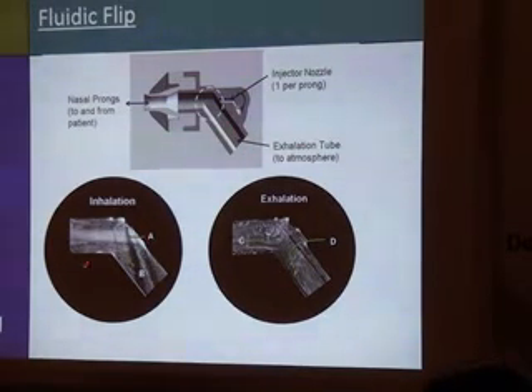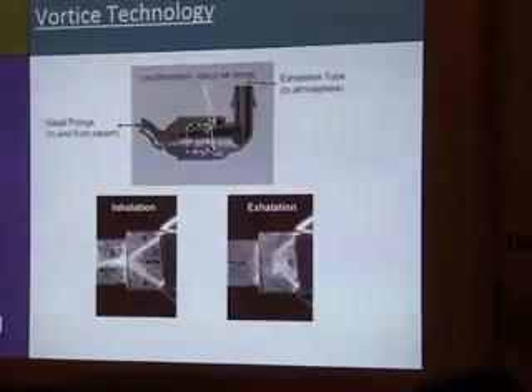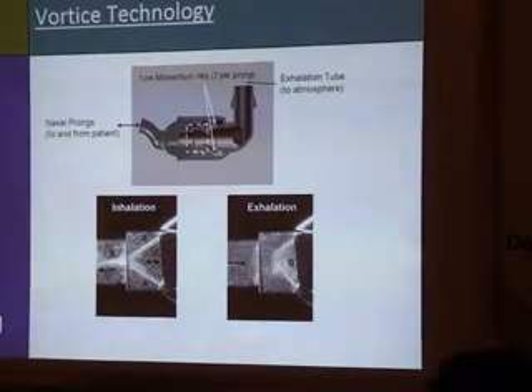So that section here is amplified during inspiration. You see these jets of air going in and the flow, and nothing happening really on exhalation. Then on exhalation, you see this dump going across as the patient is breathing out. So they're only getting the flow that they need to maintain their CPAP level. You get that nice constant CPAP level. Vortran Technology was the second company. Again, they're still all owned by the same company now. These are the masks and prongs that I prefer because they have a little bit of a flare at the end, and they seat better. But still, all your magic happens in the generator, where everything is.